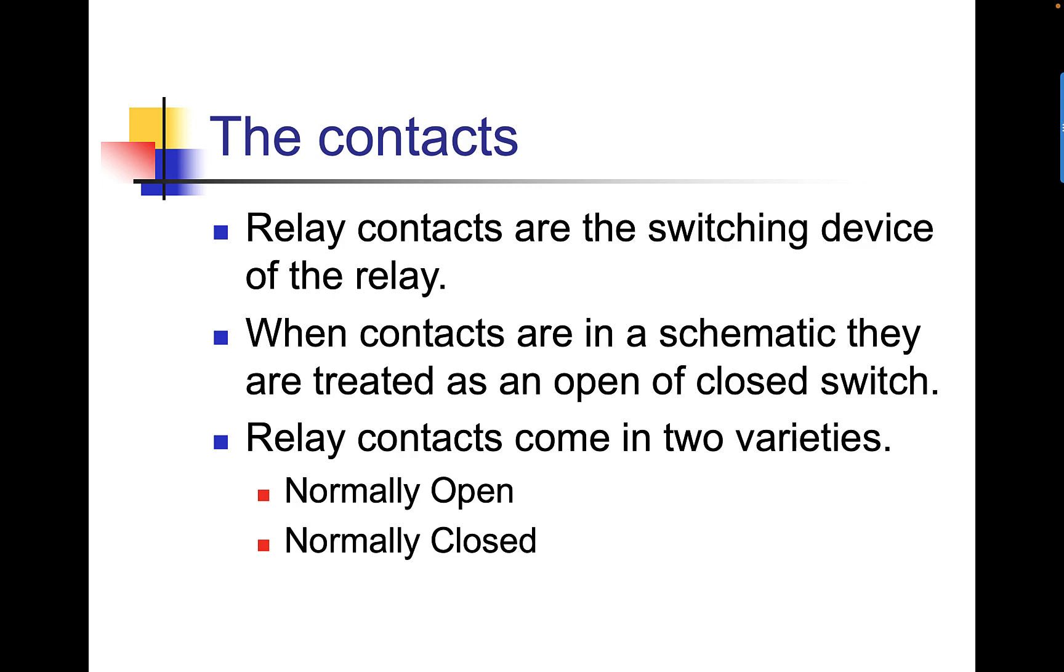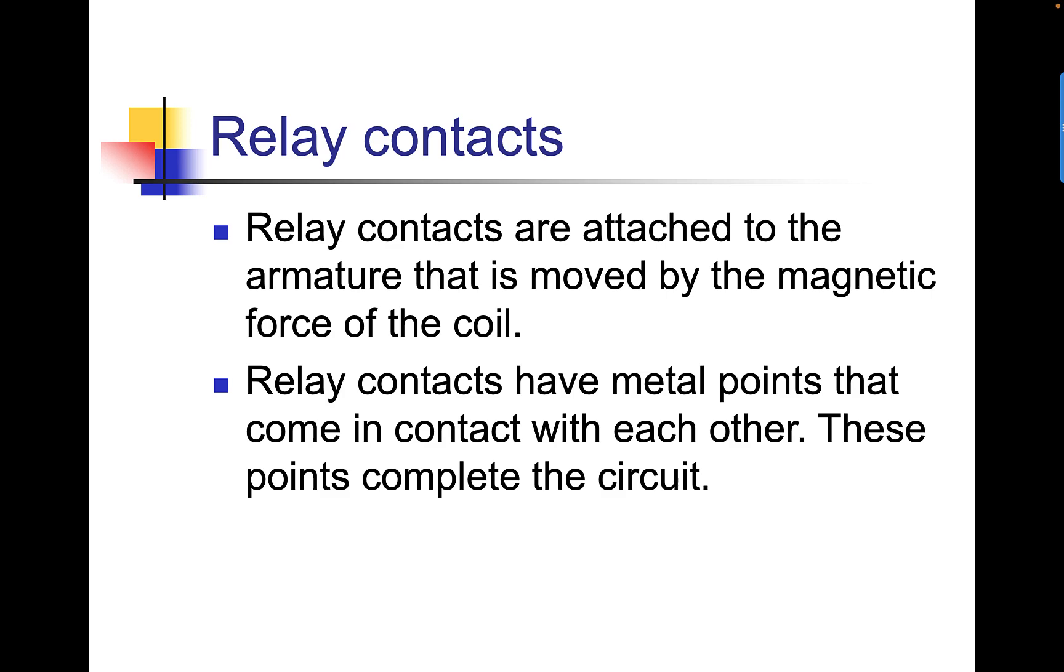When the contacts are in a schematic, they're treated as an open or closed switch. Relay contacts come in two varieties: normally open and normally closed. Relay contacts are attached to the armature that is moved by the magnetic force of the coil. The relay contacts have metal points that come in contact with each other. These points complete the circuit.